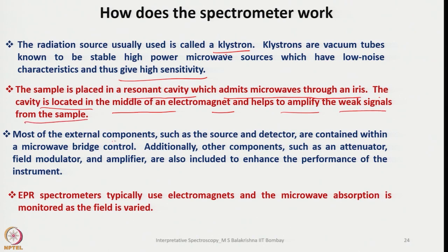Most of the external components such as the source and detector are contained within the microwave bridge control. Additionally, other components such as the attenuator, field modulator, and amplifier are also included to enhance the performance of the instrument.